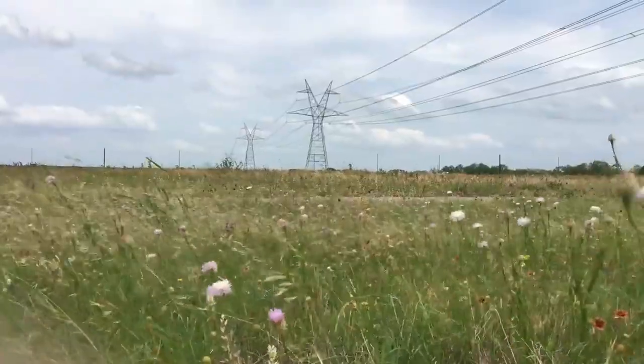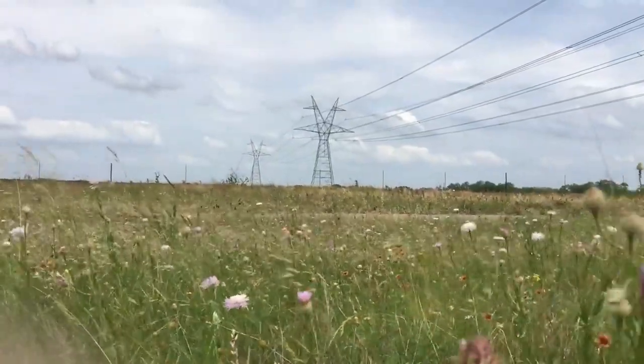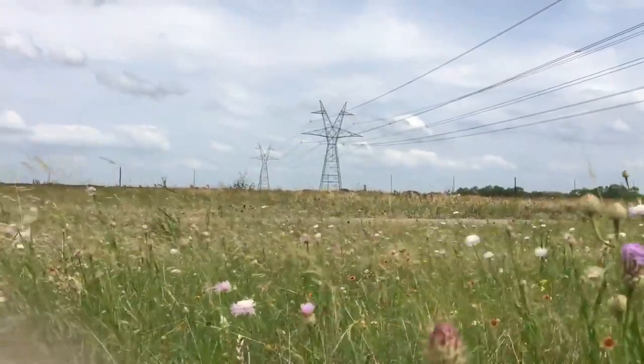High voltage isn't the only challenge associated with electric transmission lines. Just selection of the conductors themselves is a careful balancing act between strength, resistance, and other factors. Transmission lines are so long that even a tiny change in the material or size of the conductors can have a major impact on the overall cost. Conductors are rated by how much current they can pass for a given rise in temperature.